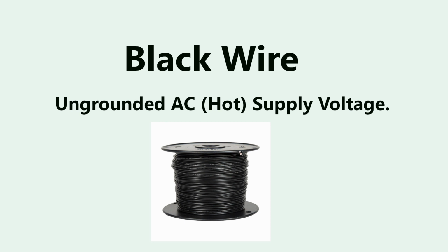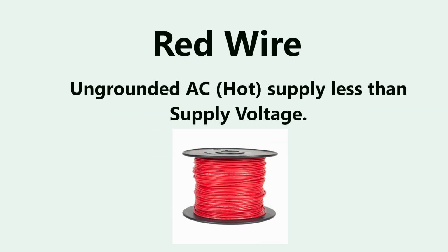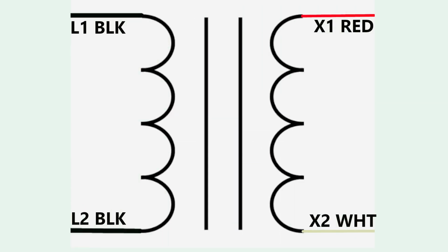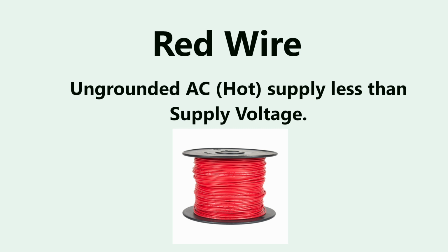Black wire is the AC ungrounded supply voltage, which means it's the hot. And red is the ungrounded AC supply voltage that is less than the incoming voltage. Okay, let's talk about an example of that. Let's say you have a panel and it has 440 volts coming into it, and you need to have some 110 volt control voltage. Well, you send that through a transformer. That means that the wire bringing the 440 into the panel is going to be black because it is the main ungrounded supply voltage. After you go through the transformer and reduce that voltage to 110 volts, that hot should then become red to identify it as not the same voltage as the incoming voltage. So that's typically what we would use red wire for.